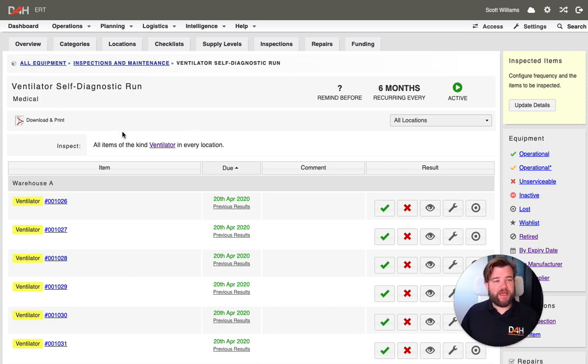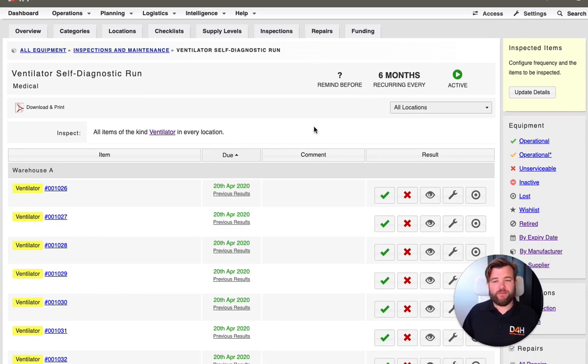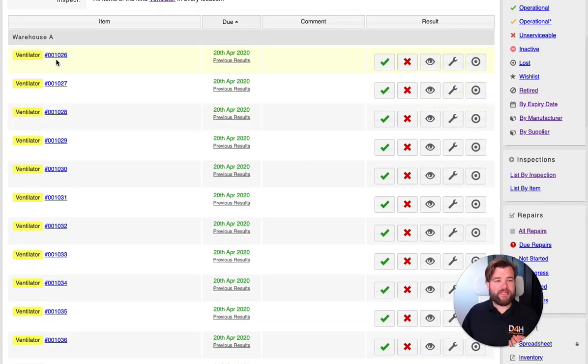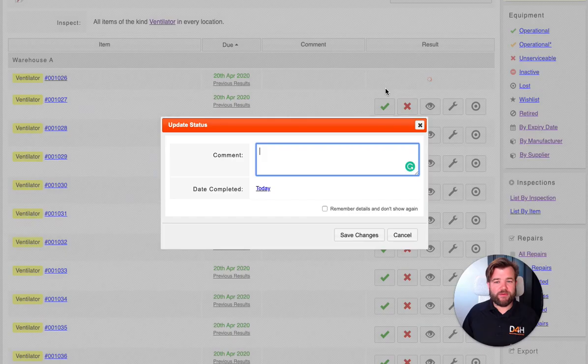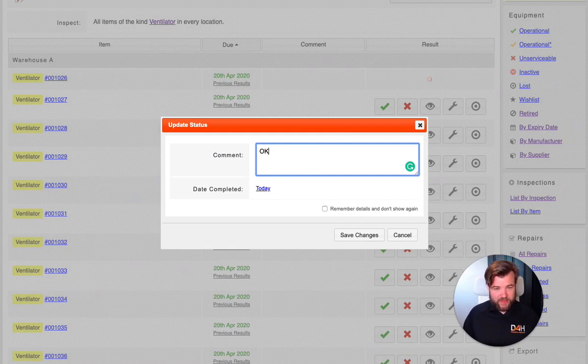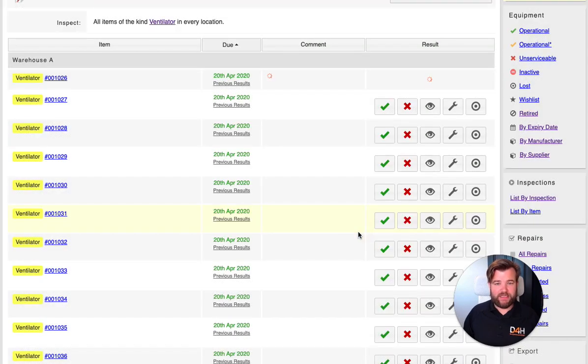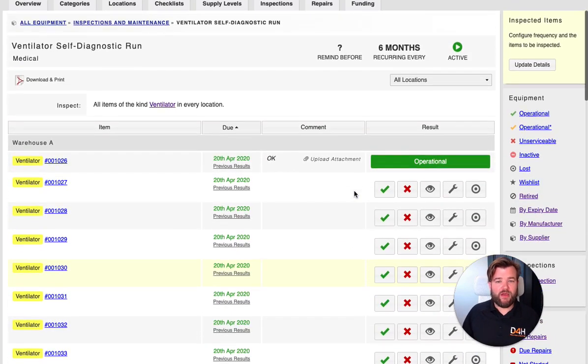You can set up inspections. So here, for example, is a ventilator self-diagnostic run. Maybe this is something I want to do every six months. It's going to remind me and prompt me by email and a notification on the dashboard in here. And then I can see all of my ventilators. And after my run is complete successfully, I can open up a comment and pass whatever I want to put in here as details that's going to audit onto the item.